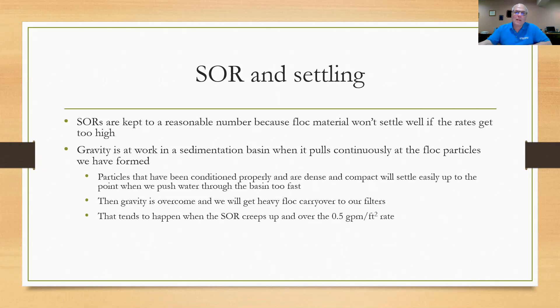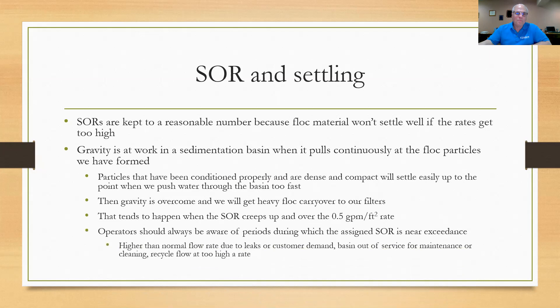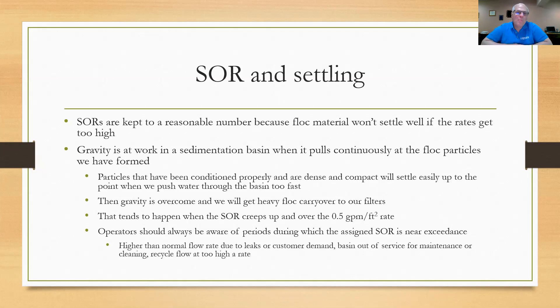That's why they want you to keep it at that rate or lower, and they'll design the basin accordingly. Operators should always be aware of periods during which the surface overflow rate nears exceedance. If you're starting to creep up to that 0.5, you need to know why. That can happen in a water plant when you have higher than normal flows brought on by a leak, or customer demand, or a basin out of service for maintenance, or when recycle flow is running at too high a rate.